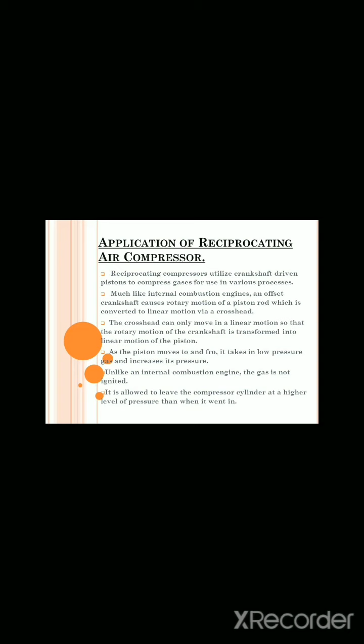An offset crankshaft causes rotary motion of a piston rod, which is converted to linear motion via a crosshead. The crosshead can only move in a linear motion, so the rotary motion of the crankshaft is transformed into linear motion of the piston. As the piston moves, it takes in low pressure gas and increases its pressure. Unlike an internal combustion engine, the gas is not ignited. It is allowed to leave the compressor cylinder at a higher level of pressure than when it went in.